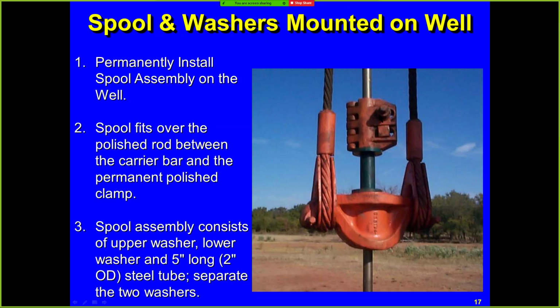So here's what the well would normally look like without the 50K load cell mounted on the well. This is an inch and a quarter polish rod. We could have an inch and a half polish rod. The spool goes around the polish rod. You've got a washer on top and a washer on bottom of the spool, and this gap is 5 inches tall. And this load cell plus the jack is 4.9 inches tall, so there's a tenth of an inch space between the top of the load cell and the bottom of this top washer when you stick it up there.